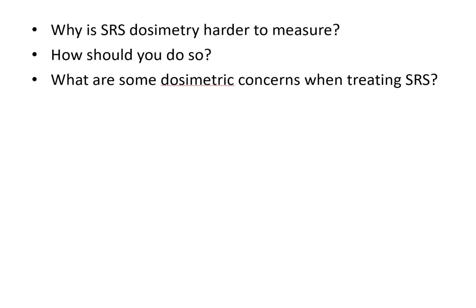SRS dosimetry is simply harder to measure because we are dealing with very small field sizes, and that leads to a lack of lateral charged particle equilibrium (CPE). This makes it difficult to measure, and there are even difficulties within dose algorithms accounting for it as well. Small fields and lack of lateral CPE just make it hard to measure.